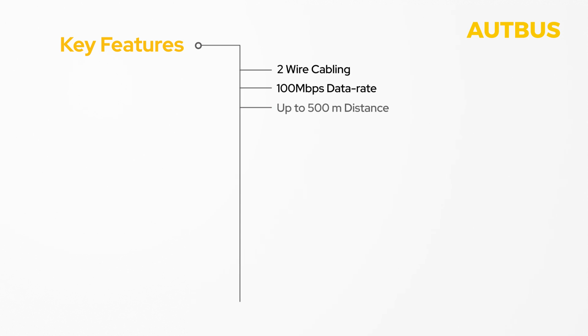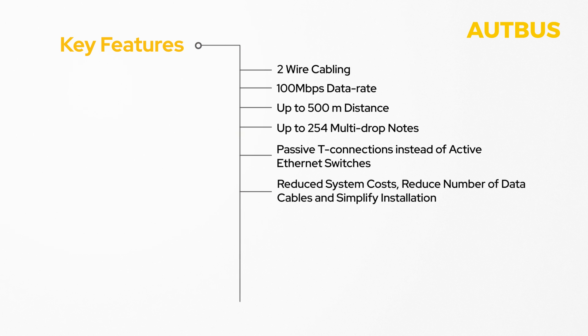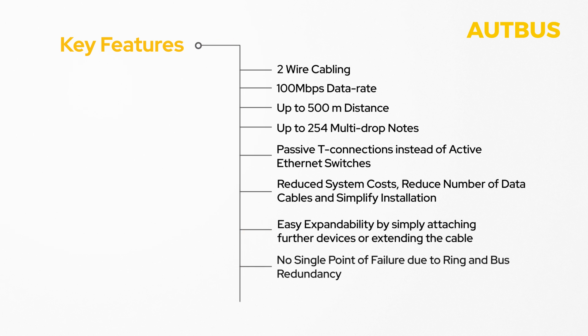The key features of AUTBUS include support for two-wire cabling capable of transmitting up to 100 megabits per second across distances of 500 meters. It allows for up to 254 multi-drop nodes and utilizes passive T-connections replacing active Ethernet switches. System cost is reduced through cost-effective two-wire cables and fewer data cables due to multi-drop connections and simplified installation. It is also easy to expand and offers no single point of failure thanks to various redundancy mechanisms such as ring redundancy, passive multi-drop connections, and bus master redundancy.